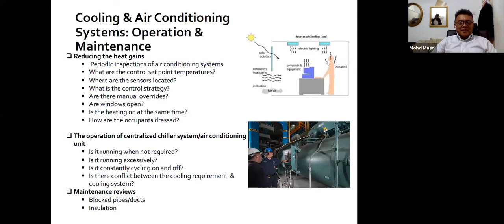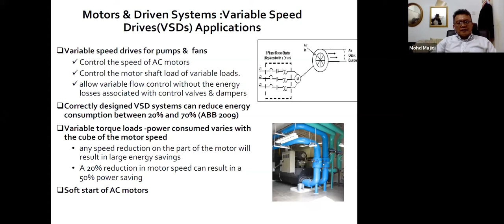For motor-driven equipment, look at whether it's possible to install variable speed drives to control motor speed, especially when the motor is oversized or the load is not constant. Putting in a VSD system can reduce consumption by 20 to 70% of actual use, and the VSD also acts as a soft start for your AC motor.